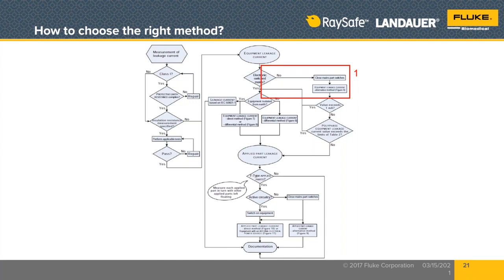So if it does not have a power switch, meaning that it's live and powered on as soon as you plug it into mains, then we have to use the alternative method for testing. No choice, we have to use it. And the alternative method, as long as the leakage current is below 1 milliampere, and in a polyphase, meaning more than single phase equipment, will follow the table in the 62353 second edition. All right, no power switch, alternative method.